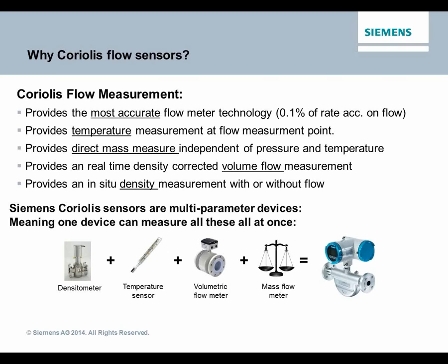Interestingly, the temperature can then be used as an output. So you can buy a Coriolis meter that measures your flow rate and use the temperature output as well. So you get 2 meters there. Now, the Coriolis flow meter provides a direct mass measure, which is another reason it's important. It does not matter whether you're measuring a pound of rocks or a pound of helium. It does not matter whether the temperature is high or whether the temperature is low. A pound will always weigh a pound. So Coriolis is the direct mass measure.